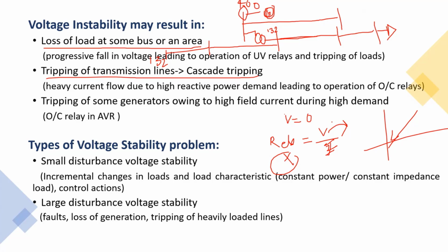So everything is good. 400 kV supporting the system and the power was transferred from this place to this radial load. What happened is that this particular ICT got tripped. Whatever the problem in the system, due to which this 400 kV support went out from the system. So what was the exact situation for that particular system? Now the entire power has to transfer through this particular 132 kV network to this place. And this was not a feasible situation, right?